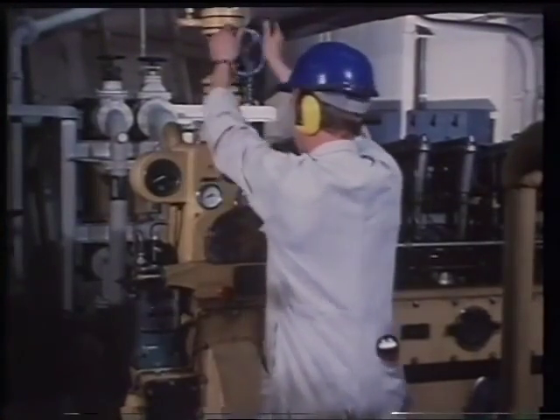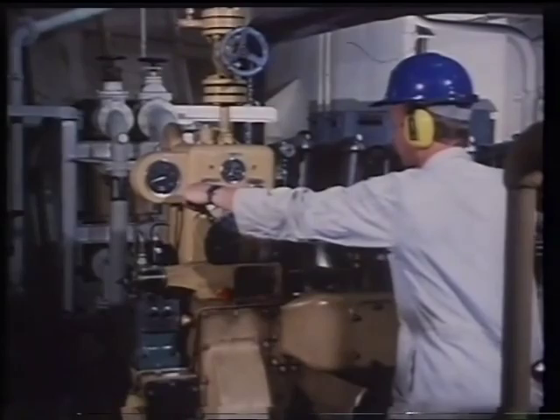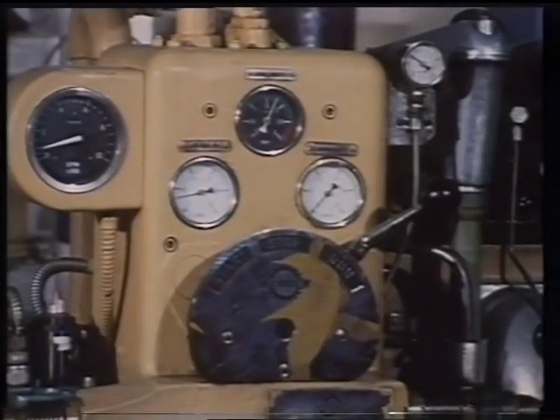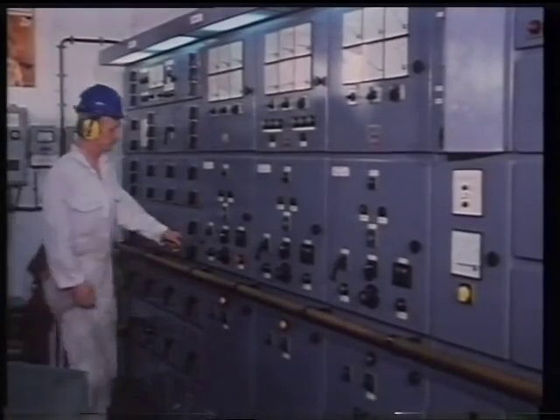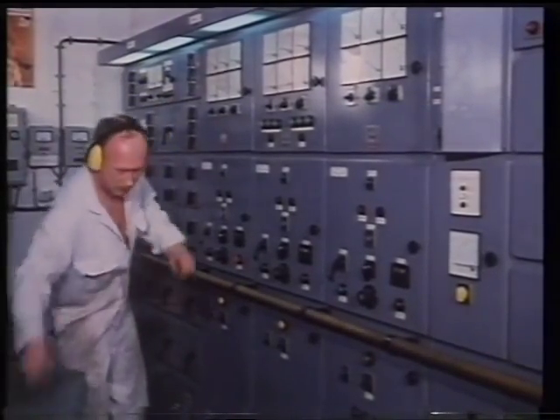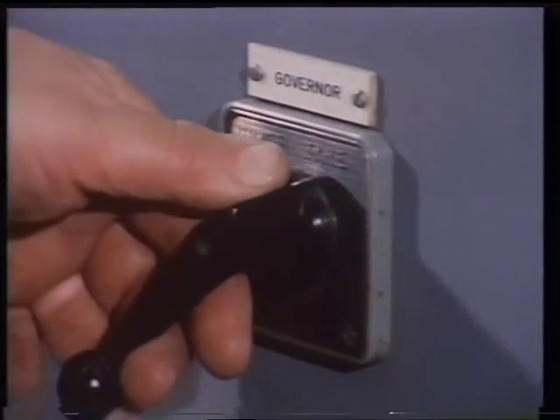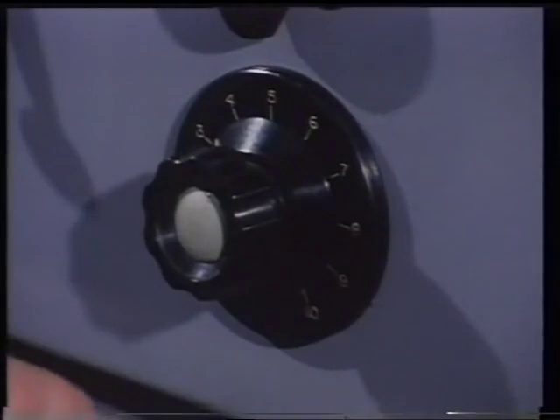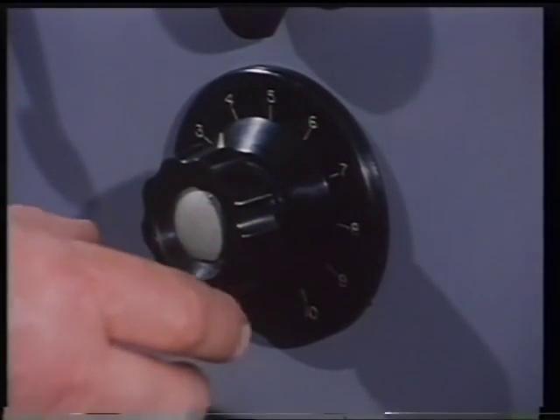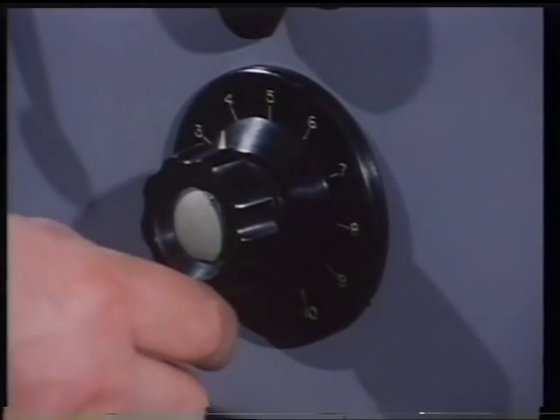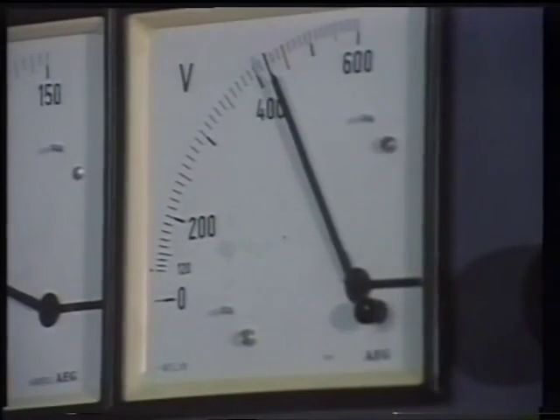Now we'll show you the synchronizing of 2 AC generators. One of the most frequent operations required involves connecting an incoming AC generator or alternator to the bus bars, which are being supplied by another AC generator. This process begins with starting up the prime mover, in our case a diesel engine. The engine is run up to speed, then the exciter current is increased until the alternator's output voltage reaches that on the bus bars. Here it is 440 volts.